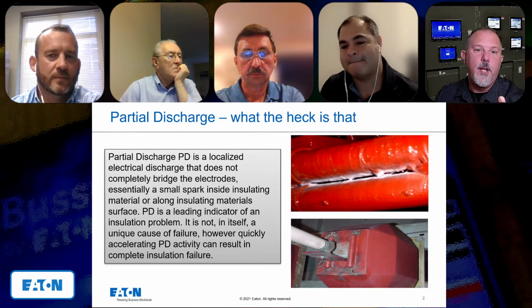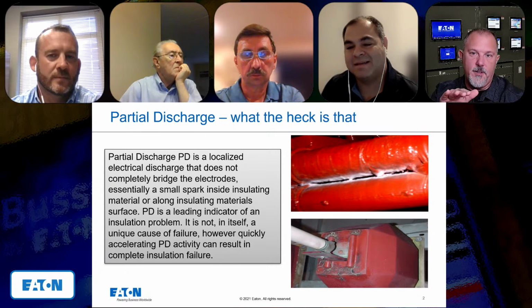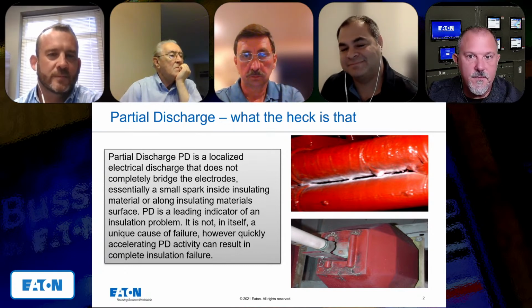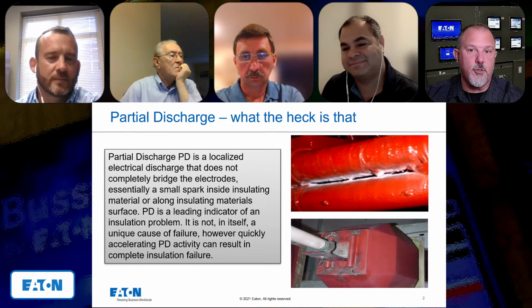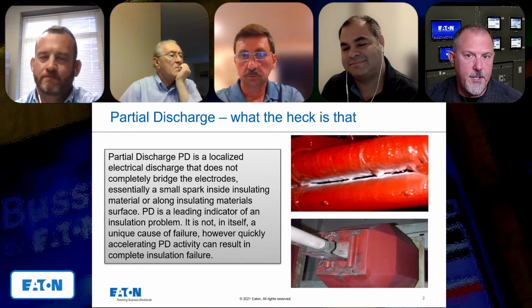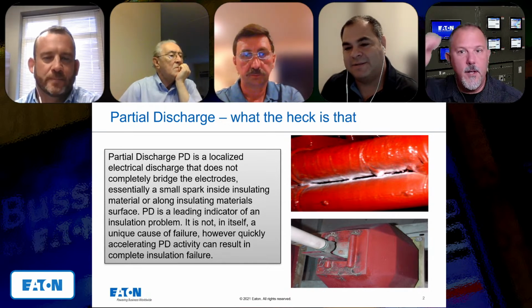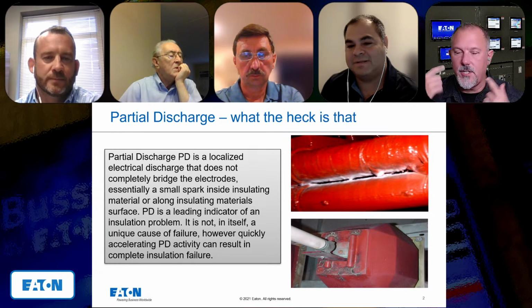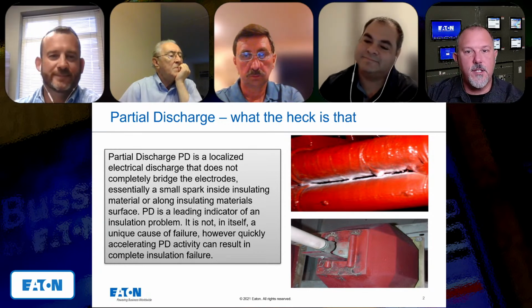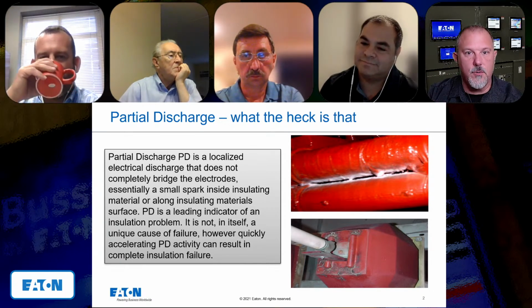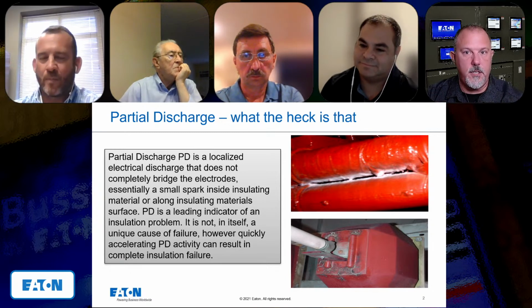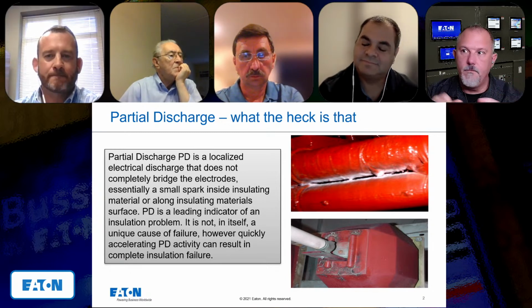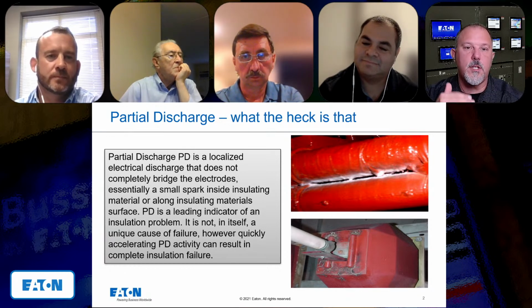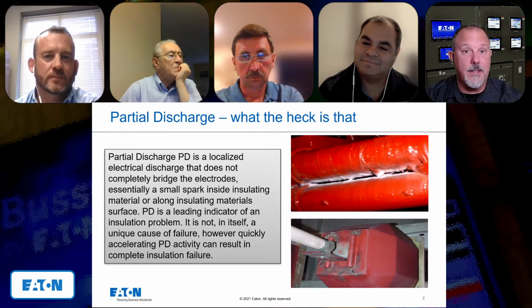What I've learned here is above 3,000 volts is critical, so I'm not going to see partial discharge on a 480 volt application. No. And I guess, because of the higher voltages and the potential difference across insulation, what you're describing as partial discharge is almost like a leakage current going through the insulation.